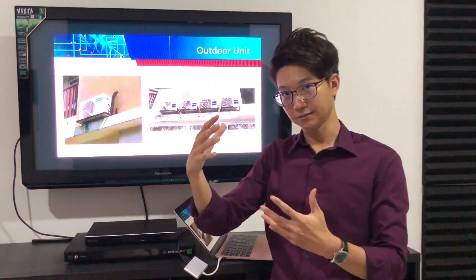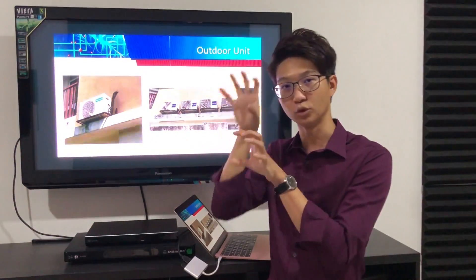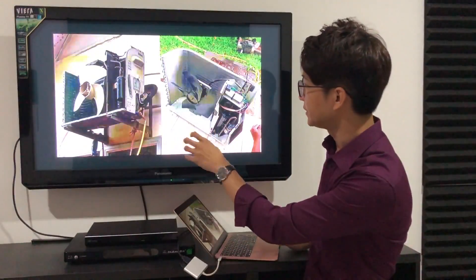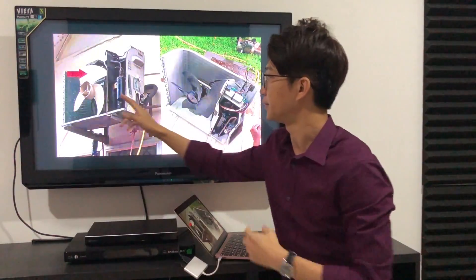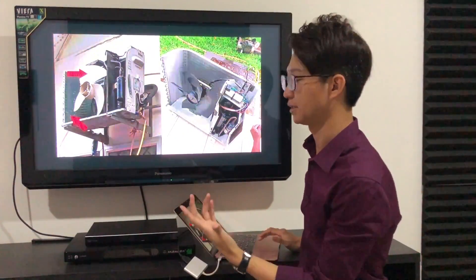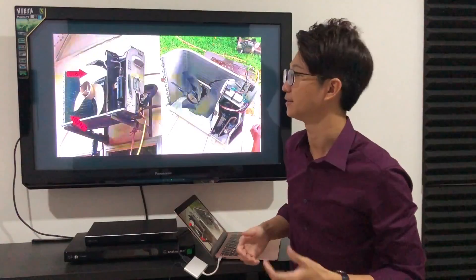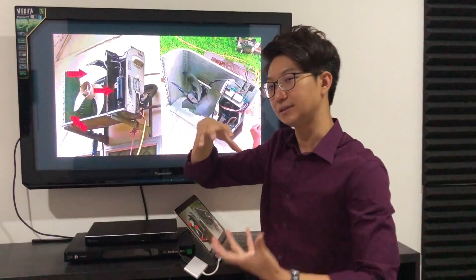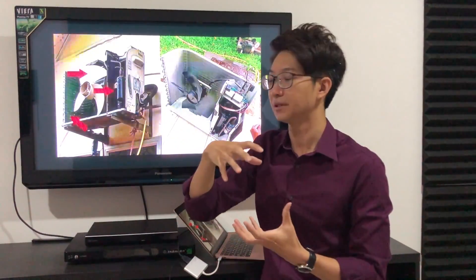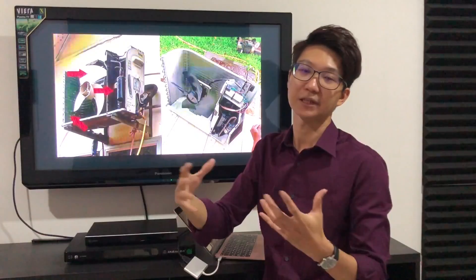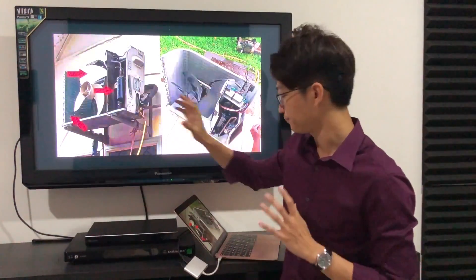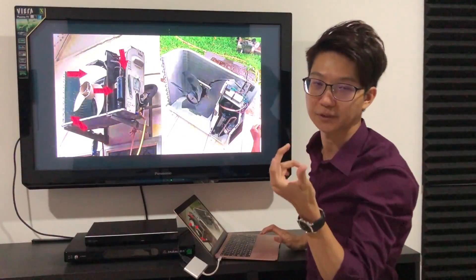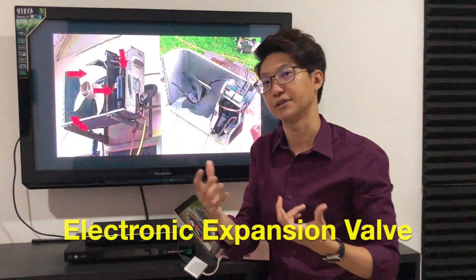The outdoor unit looks something like this — it can be bigger with more capacity. Sometimes you see a dual-fan unit; this one is a single-fan unit. If you open it up inside, it's actually quite simple: there's a big axial fan, a big fin-and-tube heat exchanger acting as the condenser, and inside there are two black cylinders — one is the compressor and one is the accumulator. The major component is the compressor. Somewhere inside there is also an electronic expansion valve.